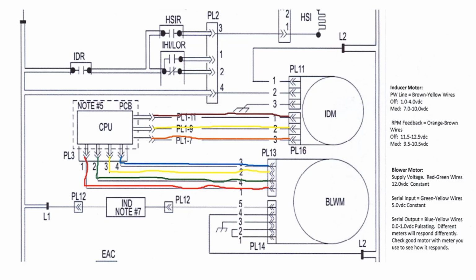And when it's running at medium speed, you will see 9.5 to 10.5 volts DC. We also see the same thing for the blower motor, the BLWM, where the supply voltage on the red and green wire will be 12 volts DC constant. The input on the green and yellow will be 5 volts DC constant. And the output back to the board will be the blue and yellow wires and will be a pulsing DC voltage from 0 to 1 volt DC.